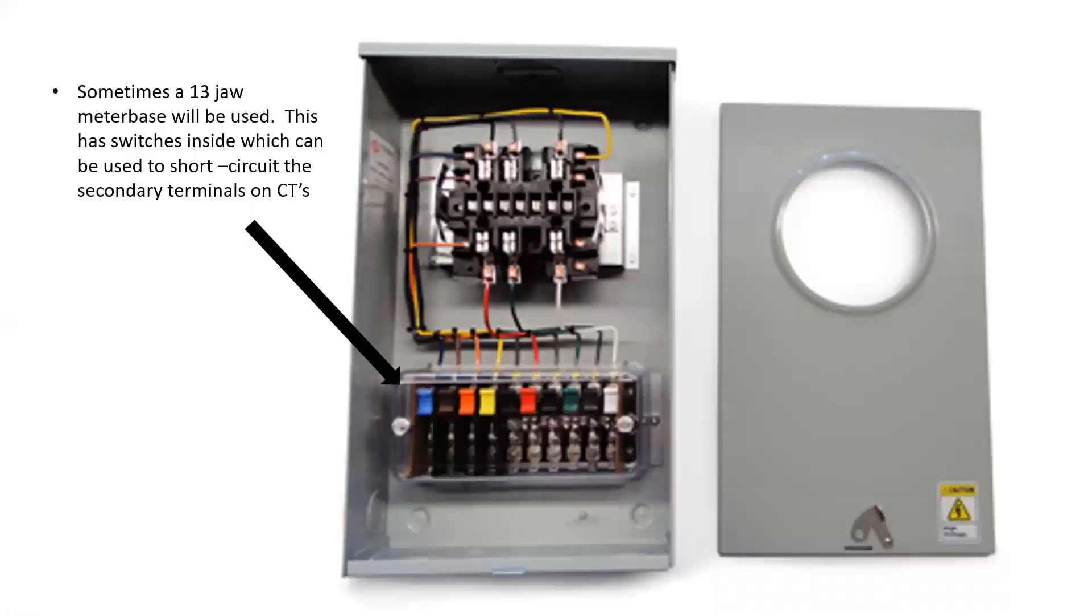Sometimes, what we're going to have is what's called a 13-jaw meter base. And a 13-jaw meter base is used because it has test switches in it. Now, it can be used with PTs and CTs, but what's helpful with CTs is that the test switches can be operated to short-circuit the CT from the meter base location, as opposed to actually opening up the CT cabinet and physically touching and moving items while they're still current flowing on the primaries. So, this can be a safer alternative.